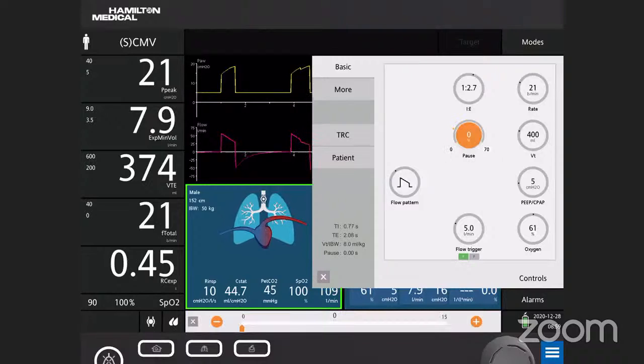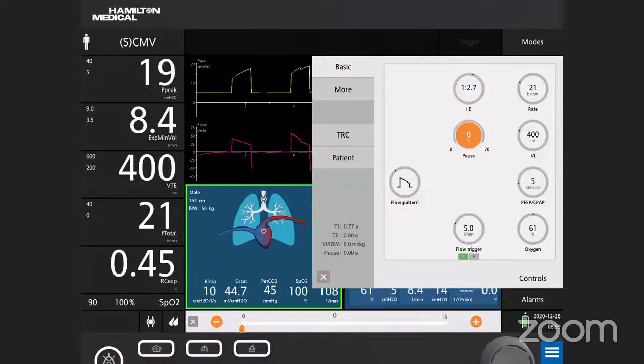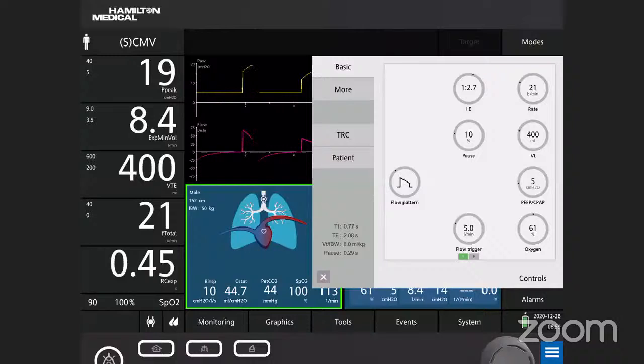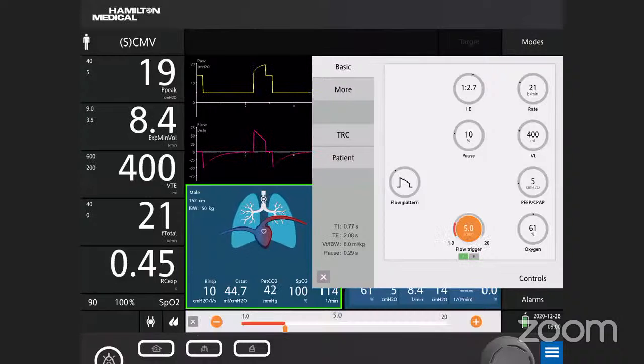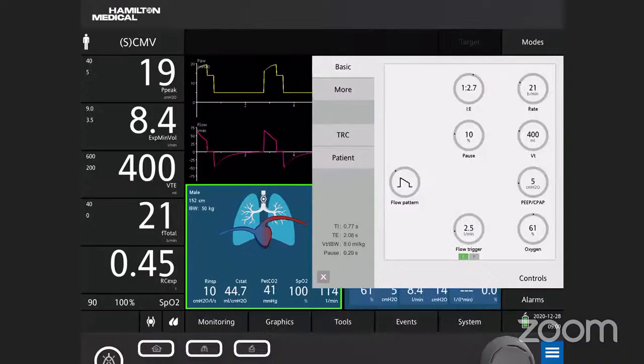We all know that if you keep a pause time, you will get the compliance of the patient, right? So you will keep a pause time of around 10% of the total inspiratory time. And then you know your trigger. You have to keep the trigger sensitivity. If it is pressure triggering, you can keep -2 centimeters of water. Flow triggering, you can keep around 2 liters per minute of flow. If you keep it very low, the ventilator will get triggered even with the presence of water vapor in the tubings. So you should keep it at around 2.5 liters per minute, or a pressure trigger of around 2 centimeters.